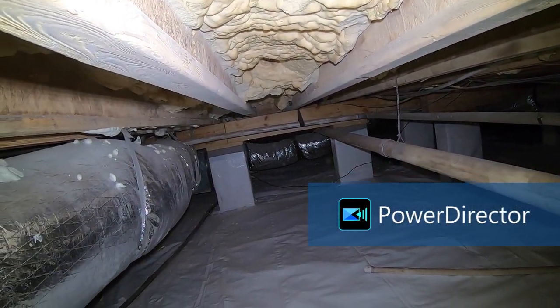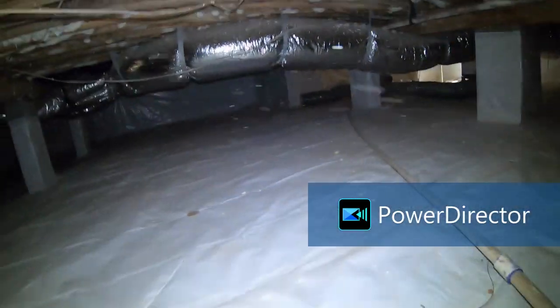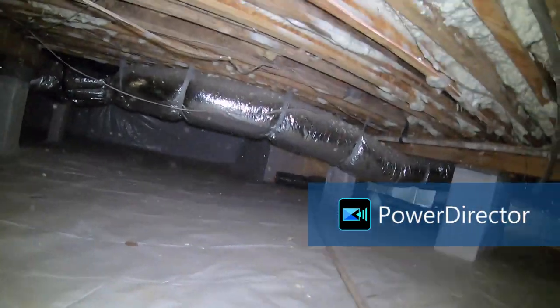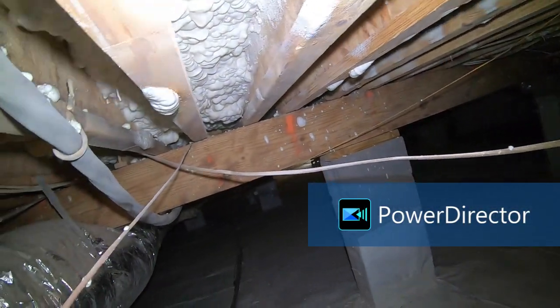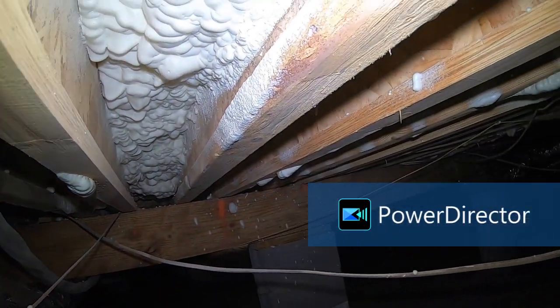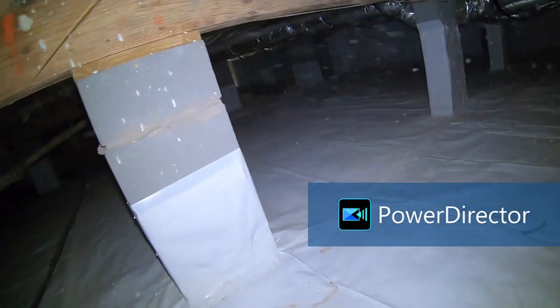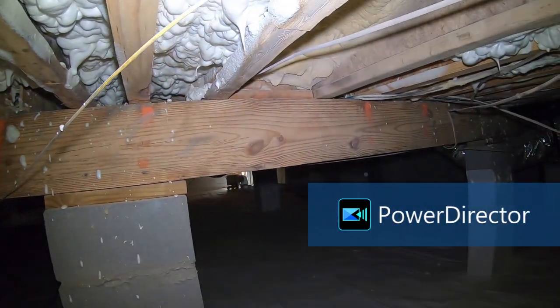And it's always interesting to get a call like this, because we're going to retrofit this crawl space, and we're going to put what's called an Atmox controlled ventilation system on this crawl space. The encapsulation company attempted to promote a negative air fan as a way to exhaust the stale air, and that's a defensive measure that they'll use once they've been called out for air quality issues. But putting a humidistat fan on this crawl space will do absolutely nothing.